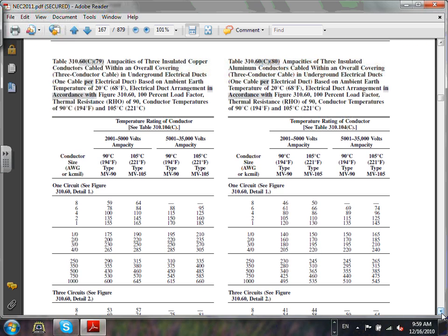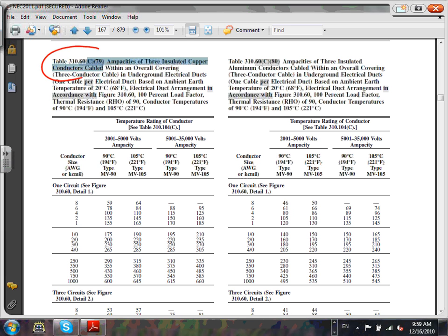Okay, can you guys go to 310.79? This is the same table, just a different name. This table is for three insulated copper conductor cable with an overall covering, in underground ducts. That's how you bring this table. This is 2011, the same table. You're bringing it underground. Here's what I'm going to bring to your attention, guys.